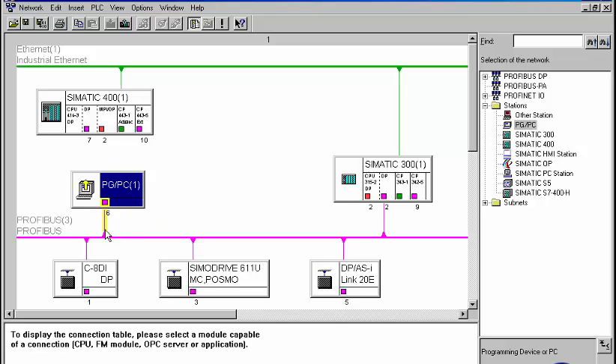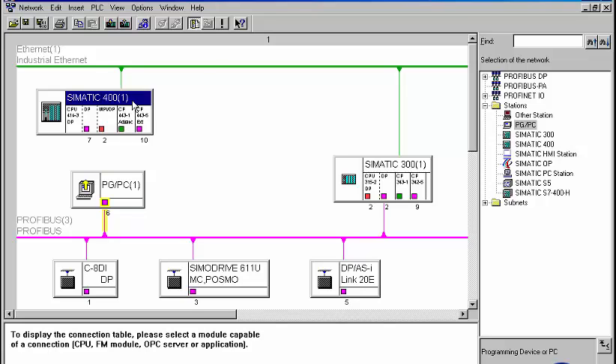We are now able to load the S7400 station with a user program, even though our programming device is only connected to the PROFIBUS. From there, PG routing and the routing-capable modules within the S7300 station enable us to reach the station to be loaded via the industrial Ethernet bus.